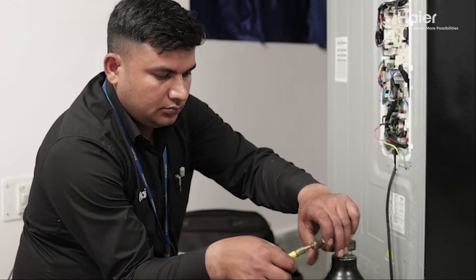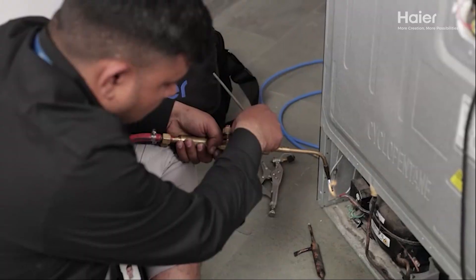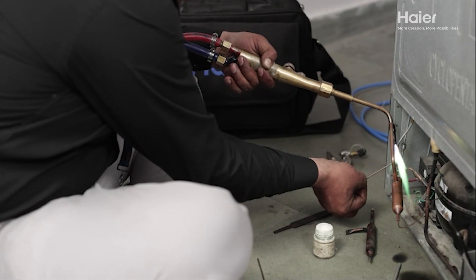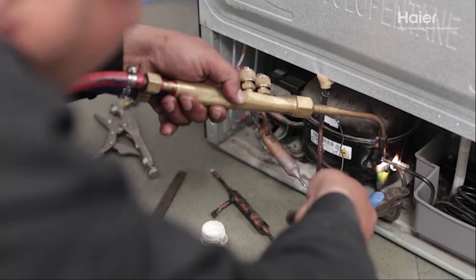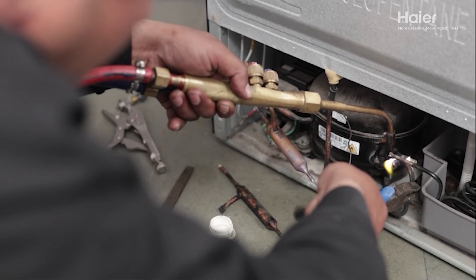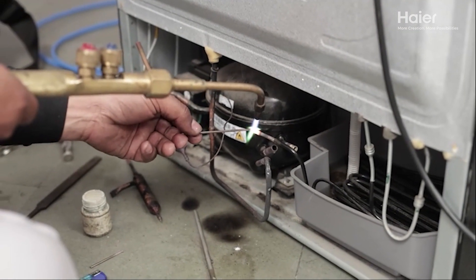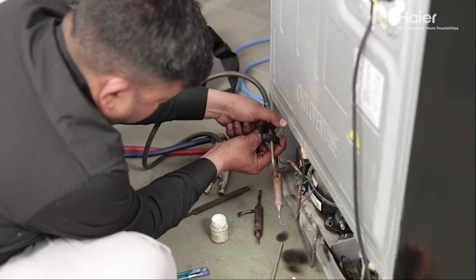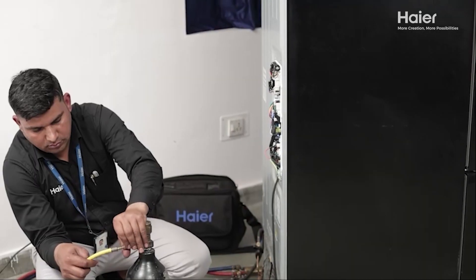Using a nitrogen cylinder, flush the condenser to ensure proper system cleanliness. Braze a new drier to the condenser and capillary port to ensure a secure connection. Block the suction port and condenser port, then use nitrogen pressure to flush the system completely.